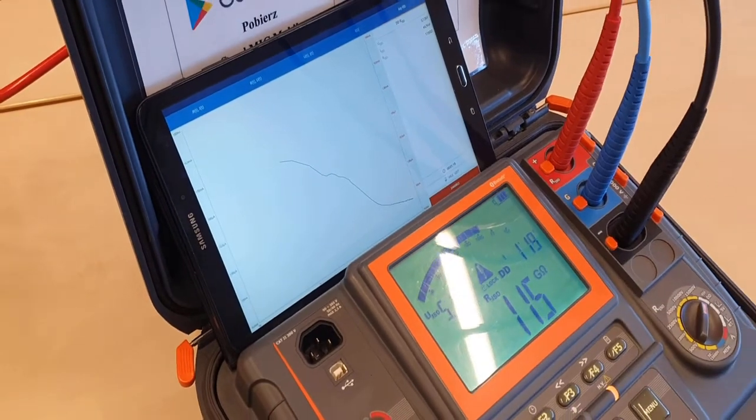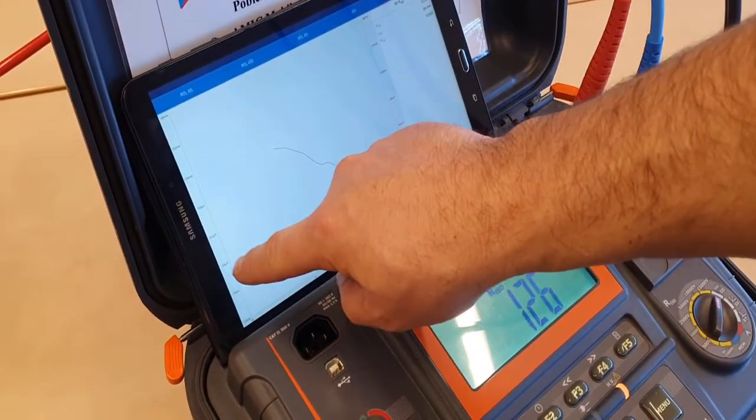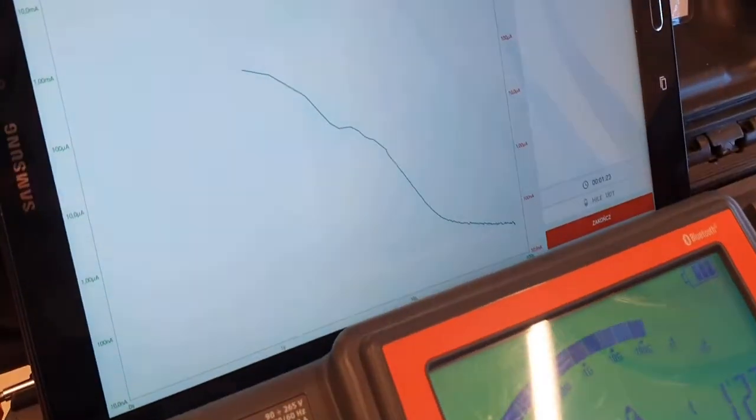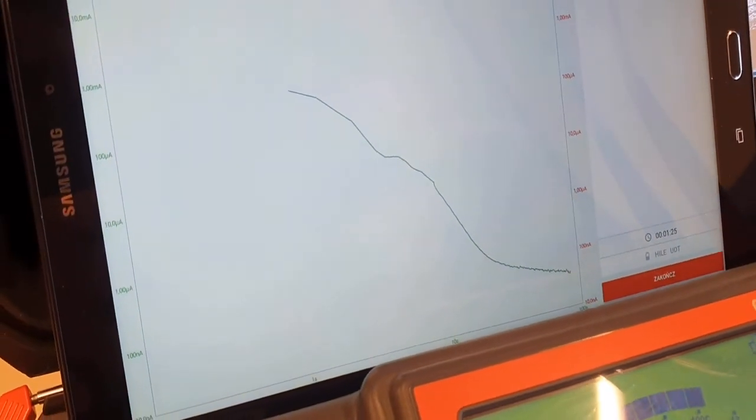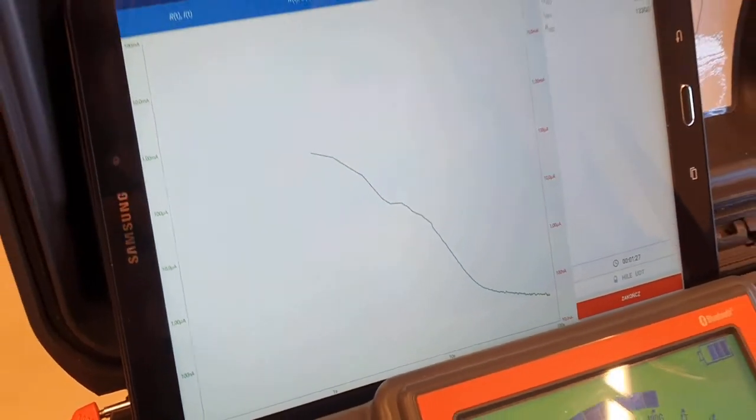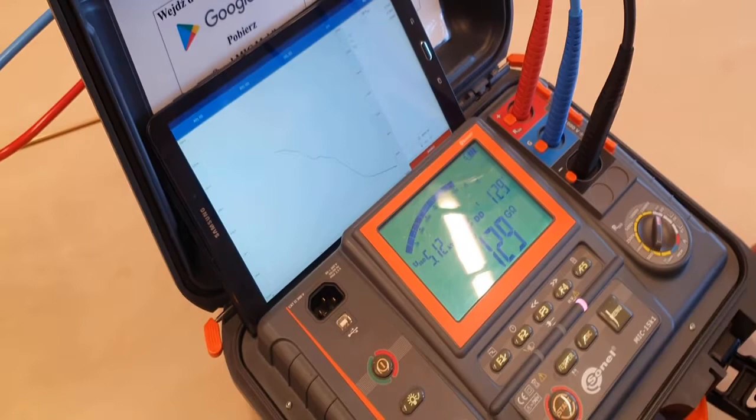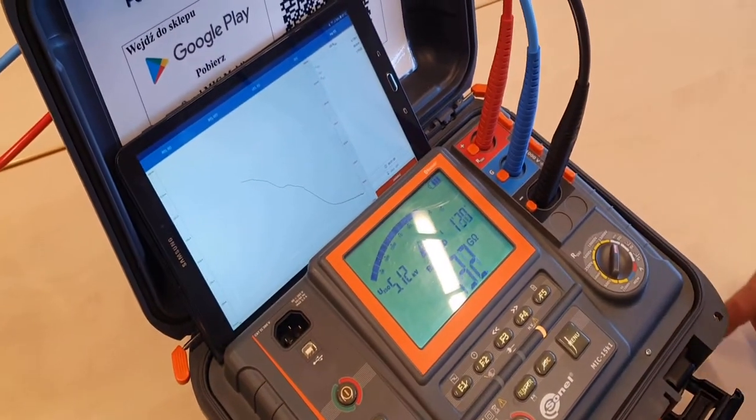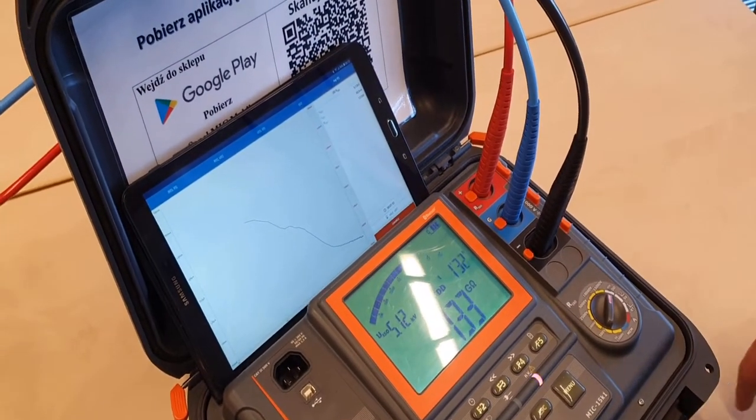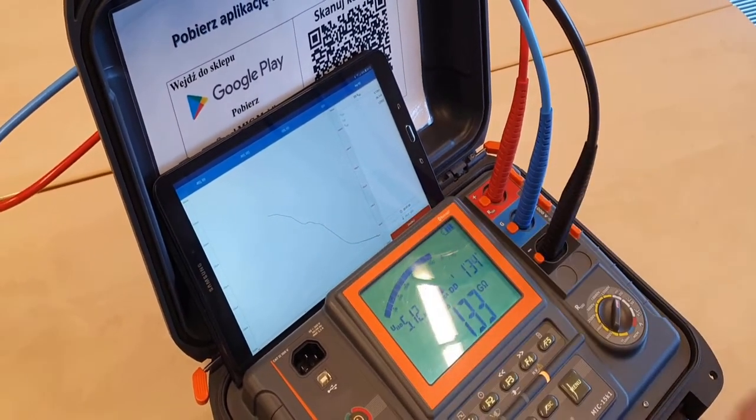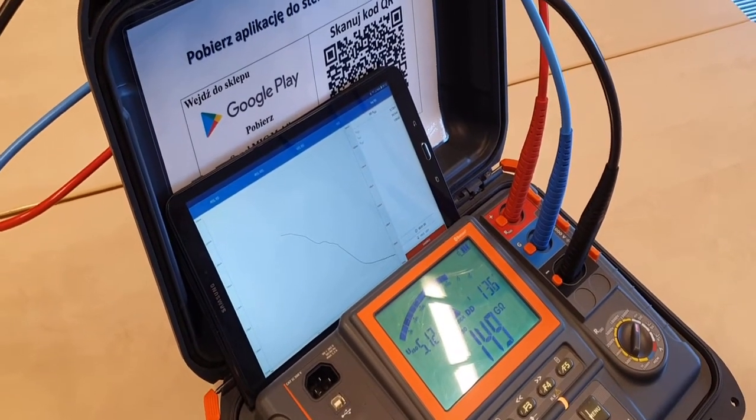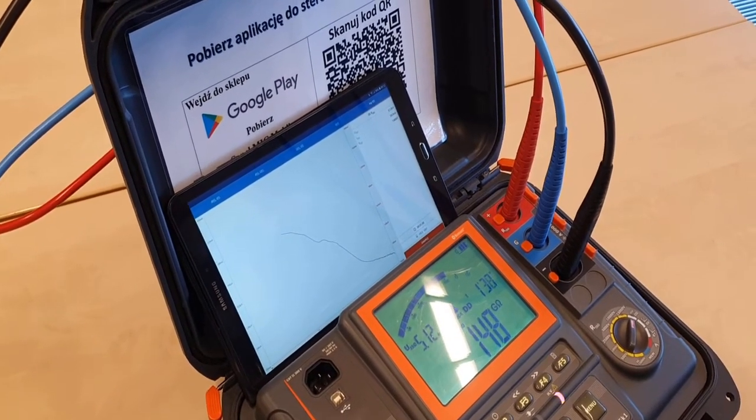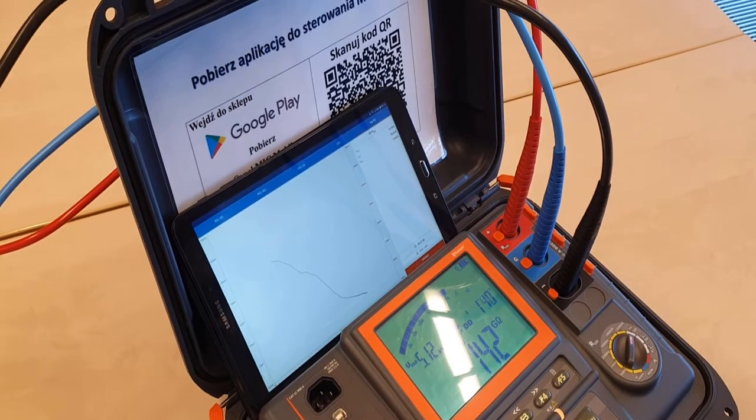Here you can see the polarization current graph, the green line. In the beginning, object capacitance was charging. Then current decreased to very low values related to the isolation leakage current. Later, in the same graph, we will see the depolarization current.